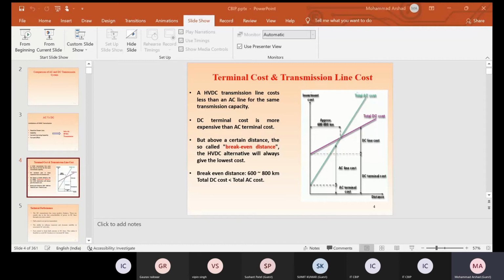This y-axis offset for the DC system is the DC terminal cost. Why? Because we need the converter equipment at the station, thyristor valves, and converter transformers. Those equipments are very costly, so the DC terminal cost is high compared to AC.